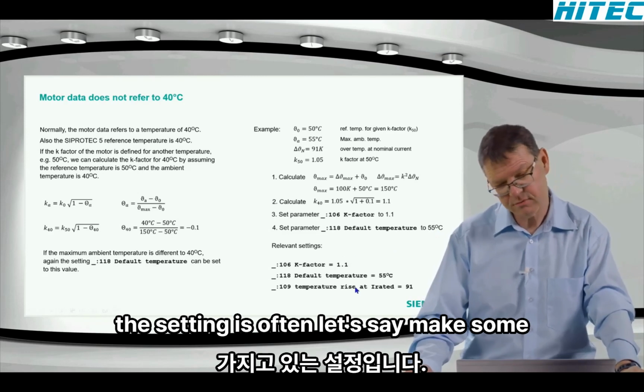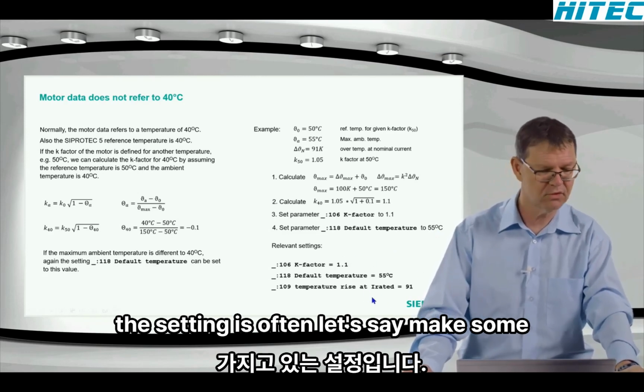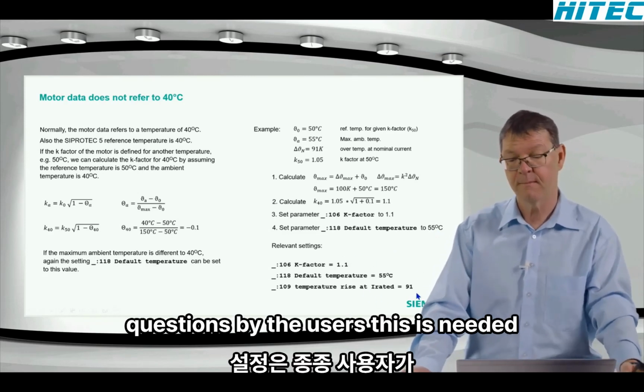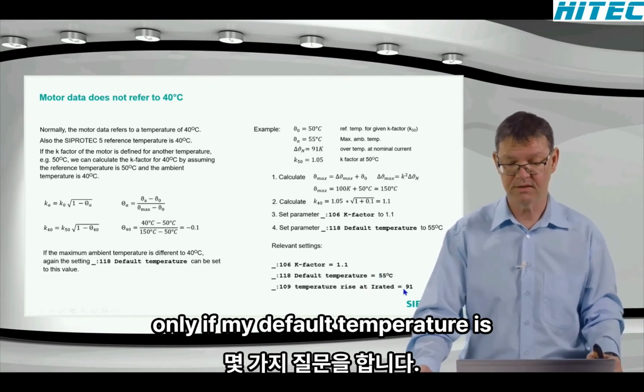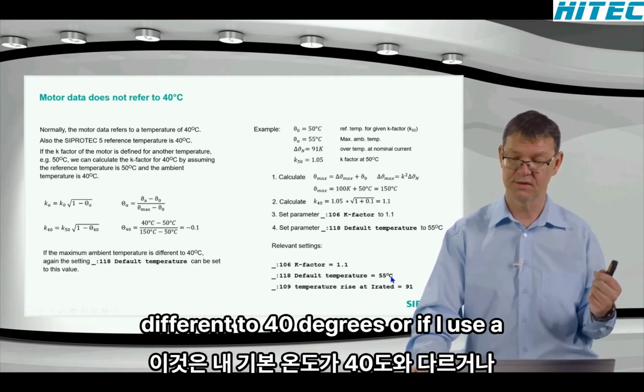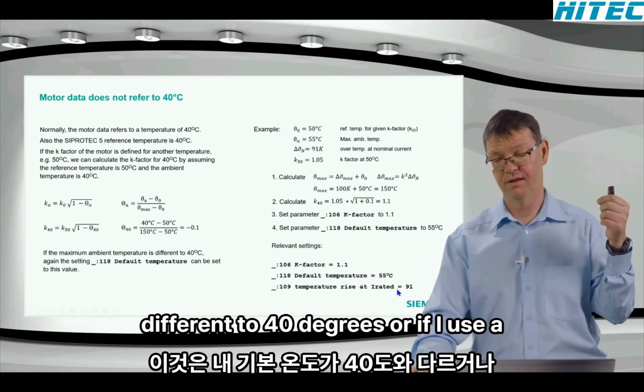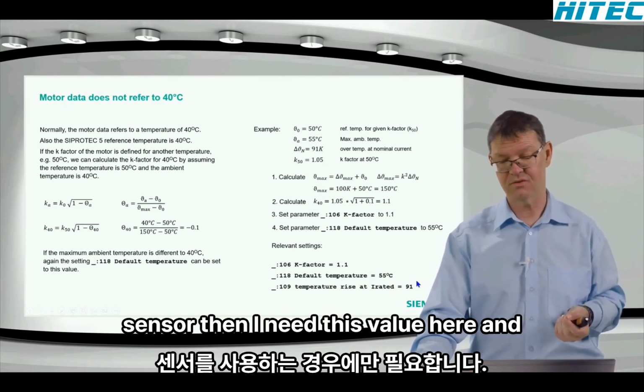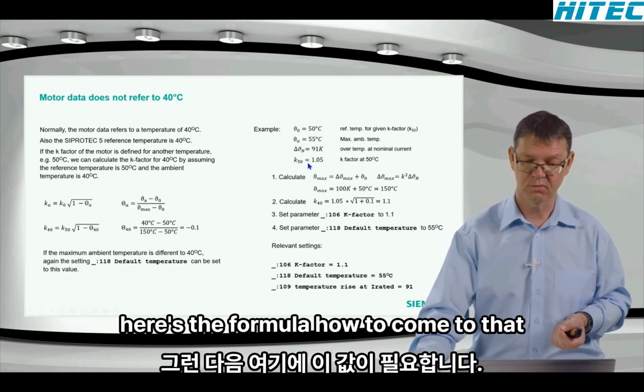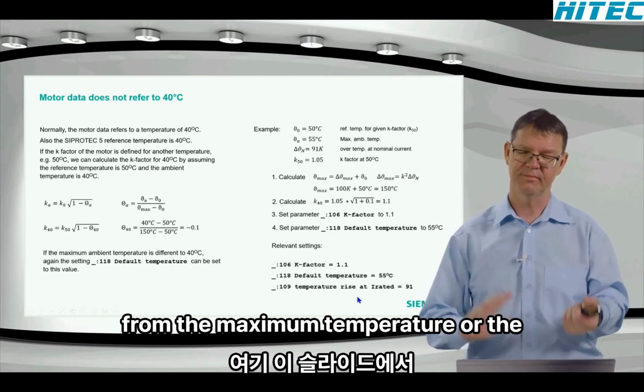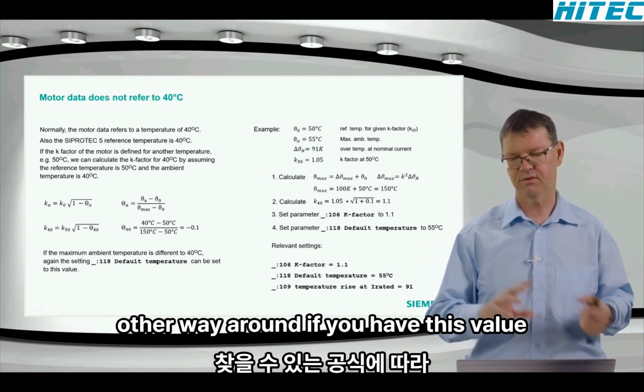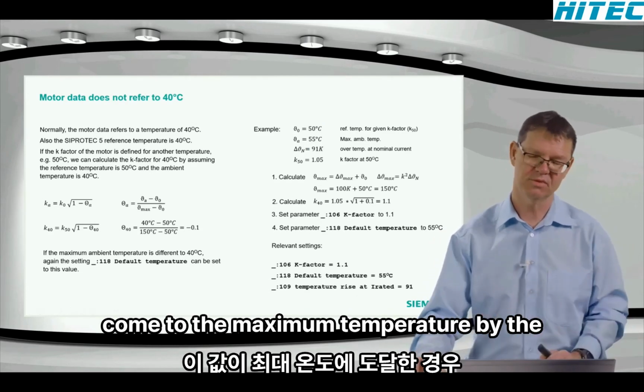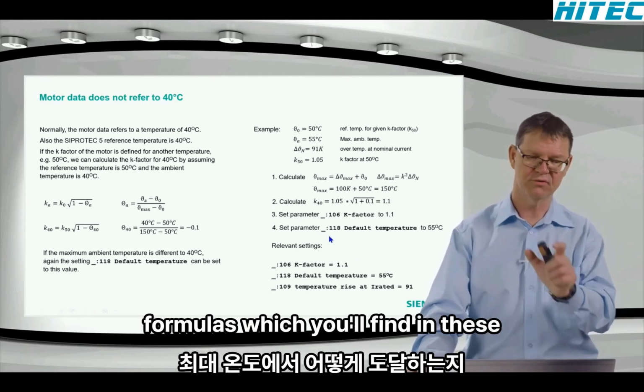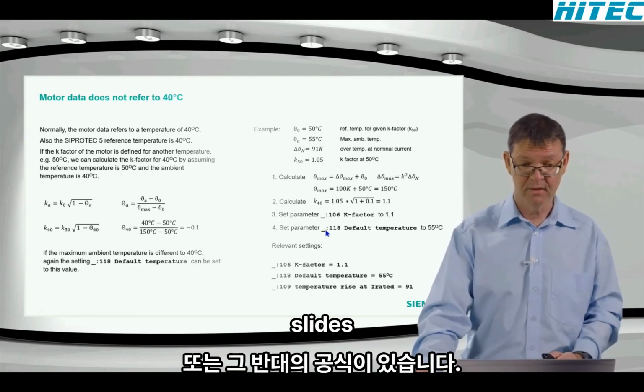This setting often makes some questions by the users. This is needed only if my default temperature is different to 40 degrees, or if I use a sensor, then I need this value here. And here's the formula how to come to that from the maximum temperature, or the other way around. If you have this value, you come to the maximum temperature by the formulas which you find in these slides.